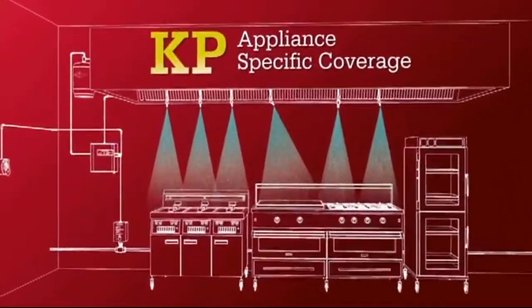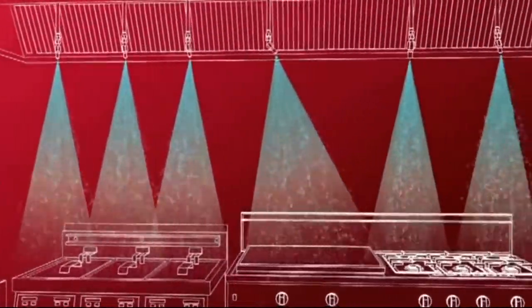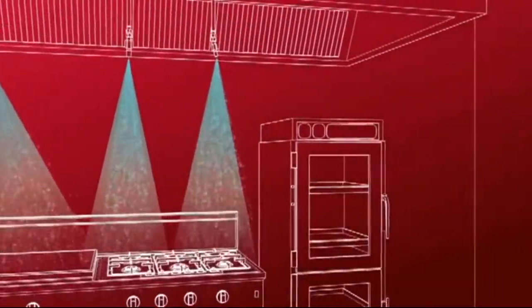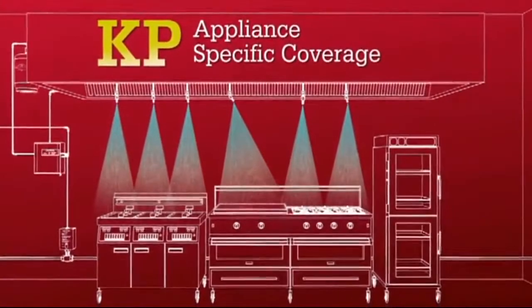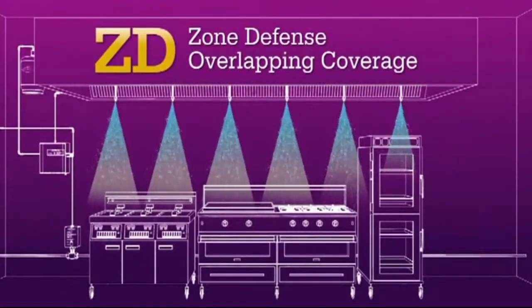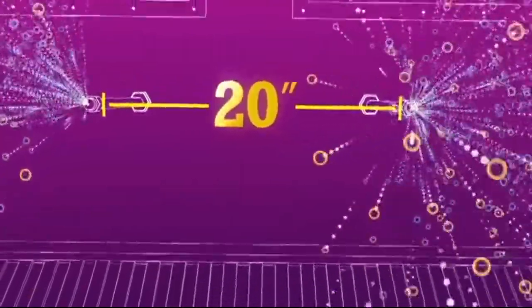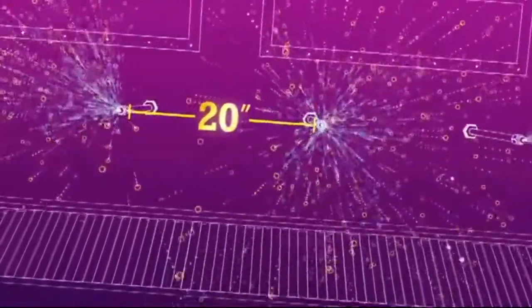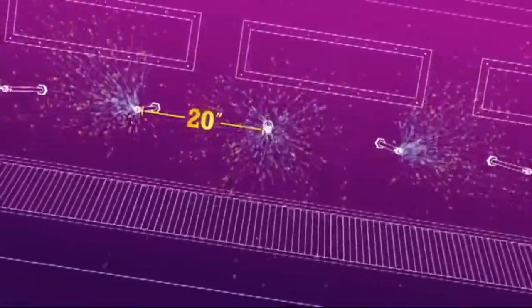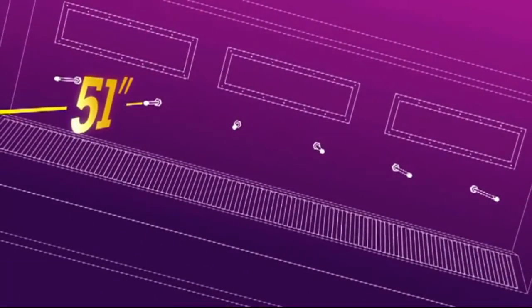Our KP option allows for customized coverage, with each appliance getting its own nozzle at a specified height, so agent only goes where it is needed. While our ZD or Zone Defense system offers overlapping coverage, in which identical nozzles are spaced 20 inches apart regardless of the appliance. This creates an overlapping discharge pattern. With the ZD system, nozzles can be placed up to 51 inches above the appliance and centered in the zone of protection.